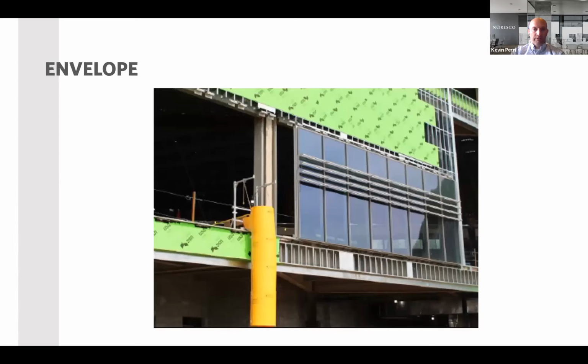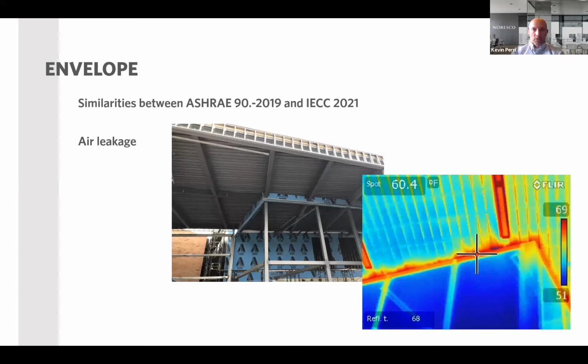So let's jump right into the envelope section. There are some similarities between ASHRAE 90.1 2019, sorry, I forgot the .1 there, and IECC 2021. And the similarity for the envelope section is air leakage. So both ASHRAE and IECC, no matter which pathway you go down, require something to do with air leakage testing. So you'll have to test your building for air leakage no matter which pathway you go down. There are exceptions to that, and I believe I'll go through that in the next slide. If not, then I'll jump back.